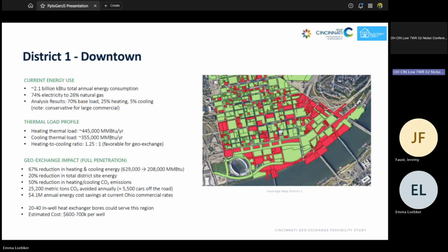So what you'll note is the downtown district represents a large majority of these facilities being high-rise or large commercial facilities. One thing I want to note is that this analysis is likely very conservative because of the nature of the regression analysis done. A lot of loads in a commercial building like this aren't necessarily weather dependent - there's a lot of people and equipment, so heating and cooling isn't just driven by weather outside but also building use. Those heating and cooling needs are probably underestimated, so everything stated here is probably highly conservative - this is a floor rather than a ceiling in terms of potential opportunity.